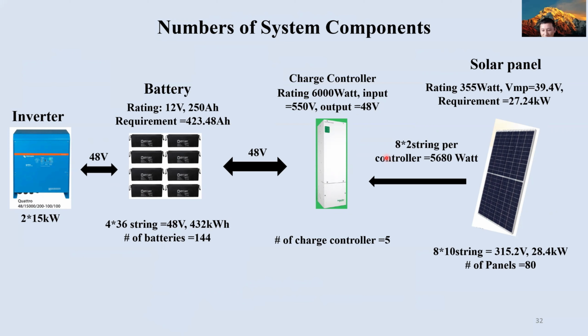Now the number of solar panels for our design: we need at least 27.24 kilowatt of solar panel rating, and our module rating is 355 watt. So we made 8x2 strings for each charge controller, because the charge controller voltage limit is 550 volt and the power limit is 6 kilowatt. In total, we have 80 panels equal to 28.4 kilowatt of rating and 5 charge controllers, with 16 panels per charge controller in an 8x2 combination.